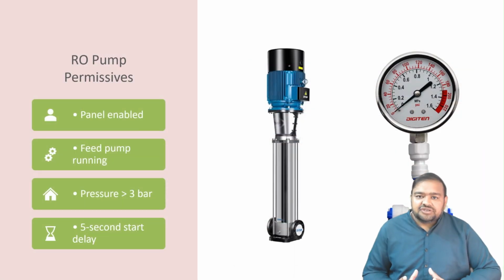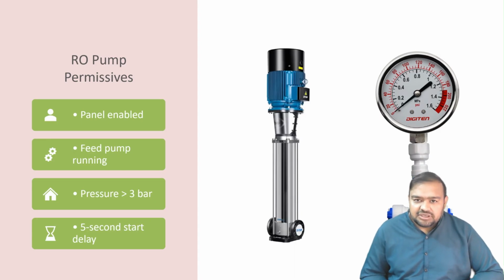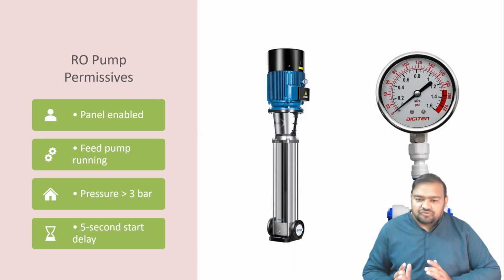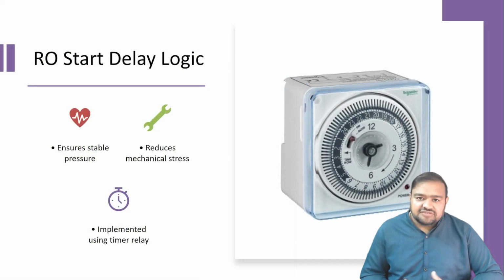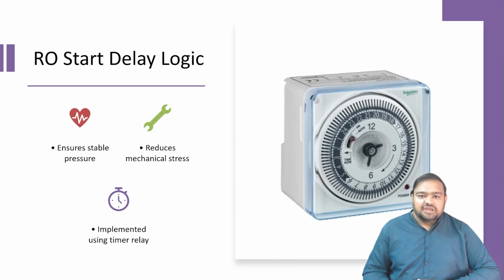The RO pump has strict control conditions. In auto mode, the RO pump can start only when the panel is enabled, the feed pump is running, RO inlet pressure is above 3 bar, and a 5-second start delay has completed. These conditions protect the RO membrane and the pump itself. The 5-second delay is not a software feature, it is a process protection requirement. It ensures stable pressure, stable flow, and reduced mechanical stress. This delay will later be implemented using a timer relay in AutoCAD Electrical.